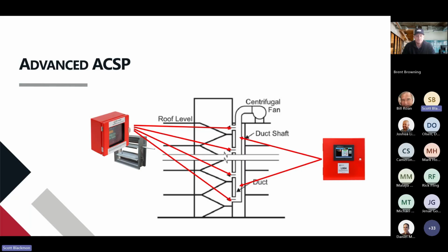Because another thing that we need to keep in mind is fire creates its own pressure. So whatever floor the fire is on, we're going to see a pressure increase of anywhere between 40 and 50%. So with zoning that off in these larger buildings, we prevent short cycling. We can also basically keep the pressure on that floor better than trying to pressurize that entire stairwell.